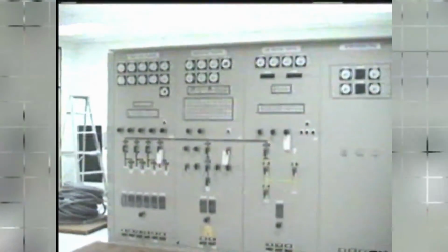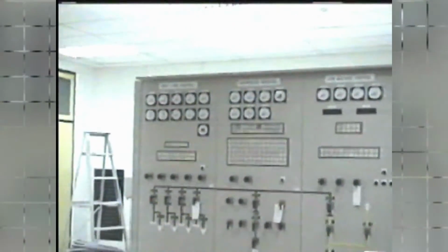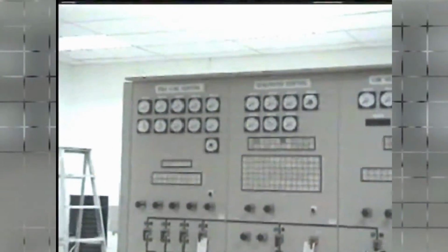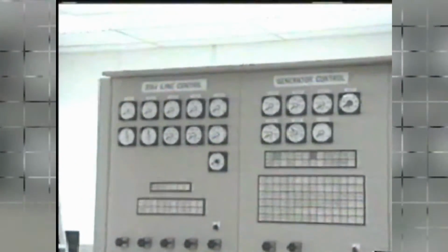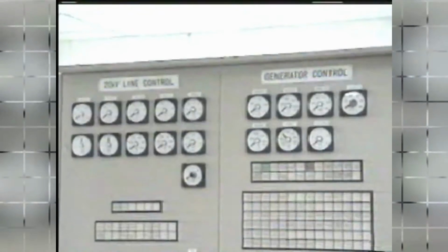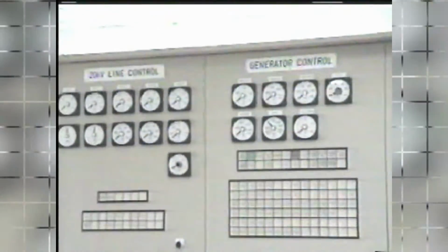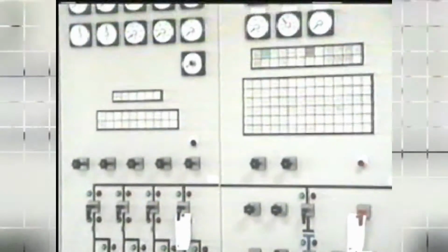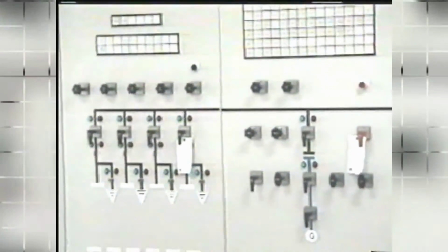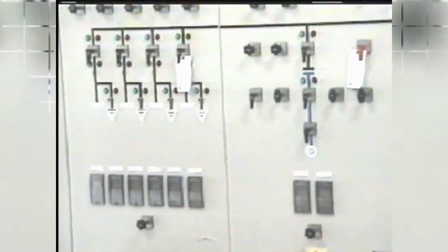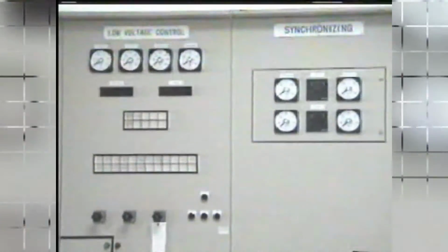A set of main control boards consists of programmable controller, electrical protective relays, measuring transducer, automatic synchronizing device, manual synchronizing panel, data logging and event recording systems, AC panels, DC panel, battery charger, and water level gauging system for intake dam water level and tail race water level. The supervisory control system consists of functions for generating unit automatic or manual control, indoor switchgear control, supervision of water levels, data logging and event recording.